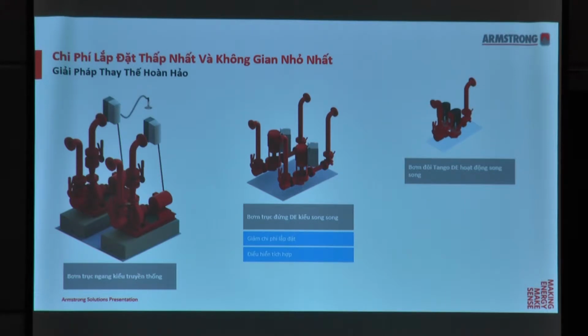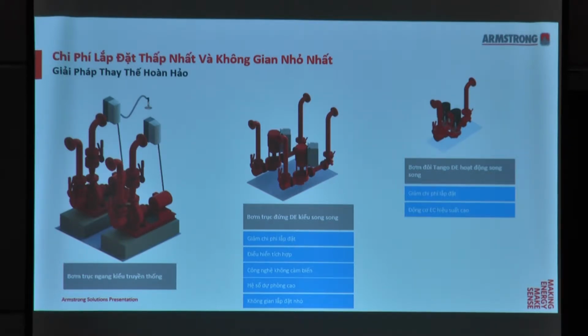Okay, so some of the advantages when you use two vertical inline pumps. One is of course reduced installed power, provided you have properly sized the pump. Integrated controls, sensorless technology, high level of redundancy, and low space requirement. And now if we go on to the next solution, Tango, again you have reduced installed power, super efficient ECM motors, sensorless technology, high level of redundancy, and lower space requirement.